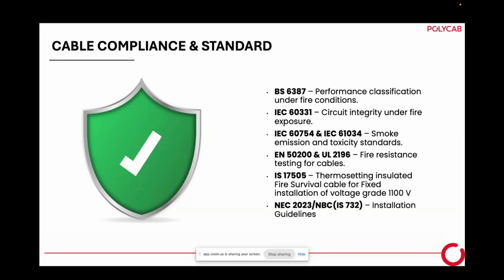Some people are still following it. Whenever a customer thinks that in a fire the temperature does not go beyond 750 degrees, they can install fire survival cable as per 60331. IEC 60754 and 61034 are basically halogen toxicity emission and smoke emission tests. Then EN, a new norm has come, EN 50200. That is basically a testing method, and is quite similar to 6387. And UL 2196. UL 2196 is more stringent, because its circuit requirements are more stringent. But more or less the whole fundamental idea of testing is the same as 6387.